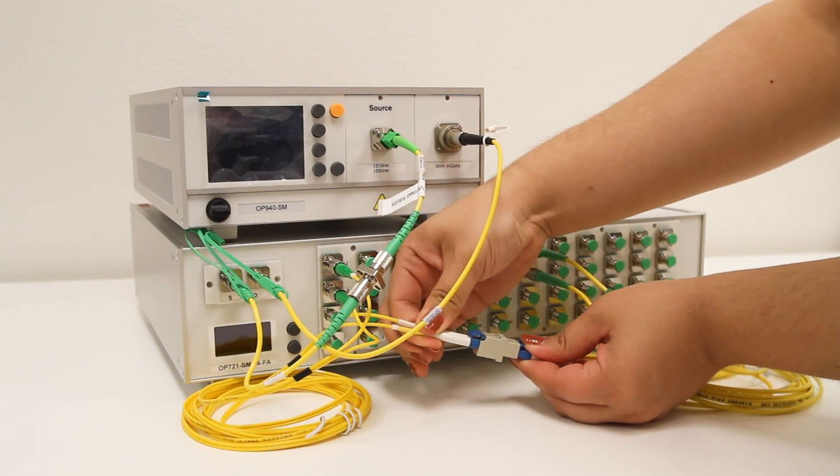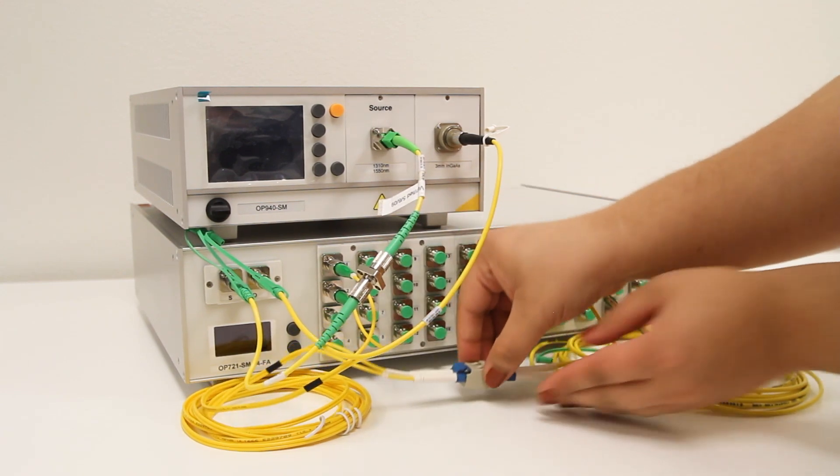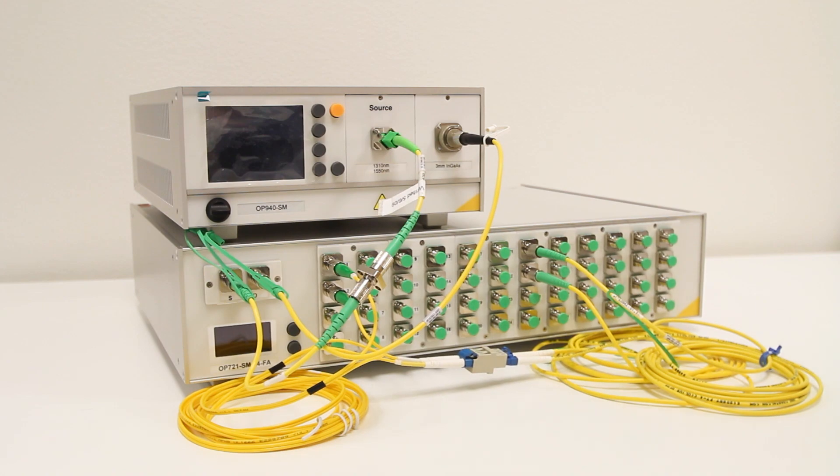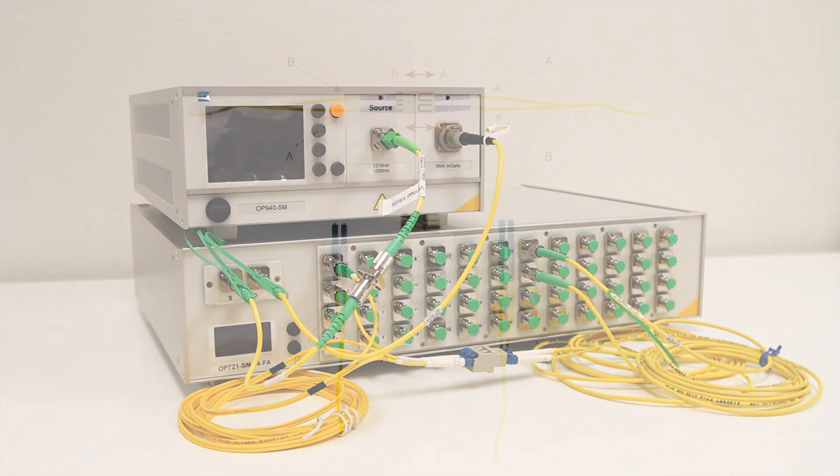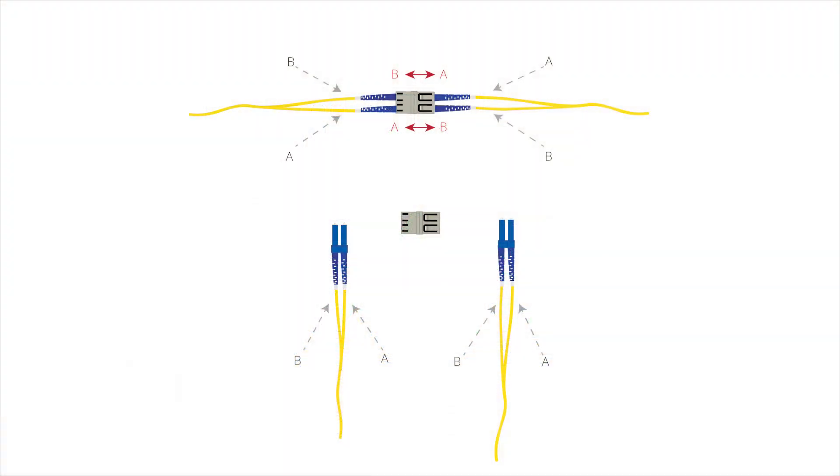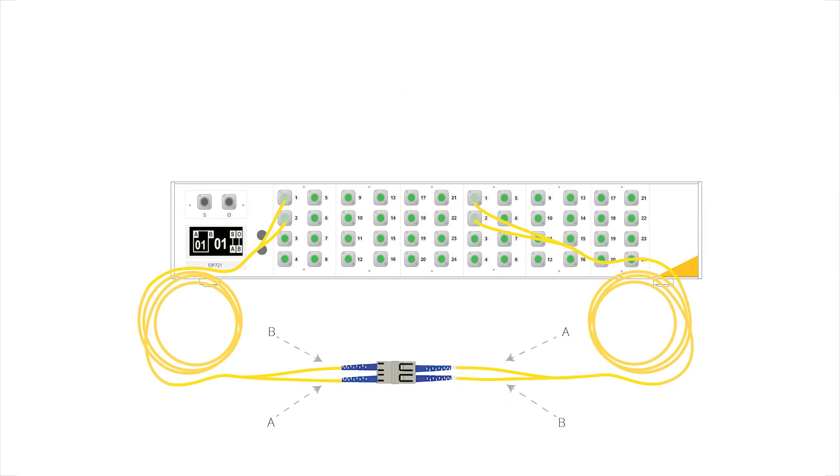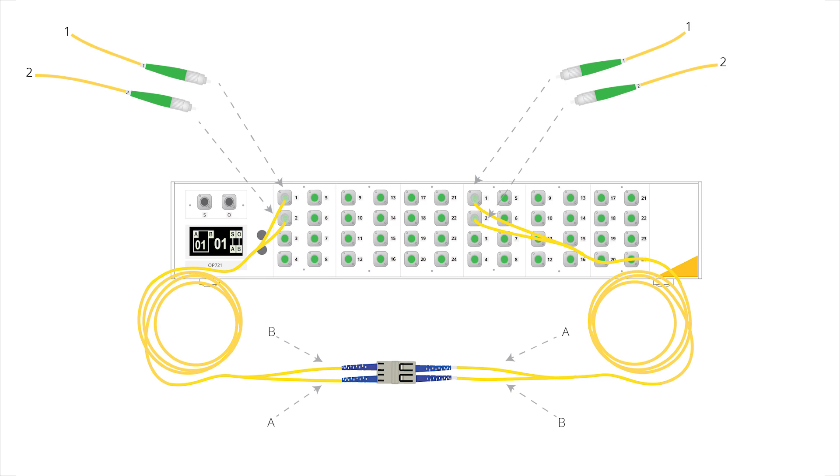Before we continue, let us address an issue that can arise when these reference cables are connected together. Within the duplex LC housing, the LC connector on the right is always the A connector, and B is on the left. A and B correspond to 1 and 2 labels on the FC side of the reference cable respectively.